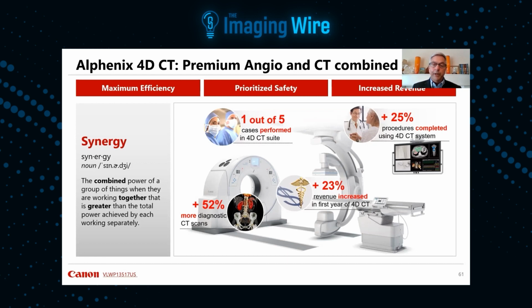And part of the reason was, right now, a lot of departments that do interventional CT use what's called CT fluoro, and they'll have a CT scanner that's dedicated. It might be outside the department or way down at the other end of the department. And they'll have to dedicate that CT scanner to just doing those types of cases. And that means that they have to buy extra CTs to do their diagnostic CT, all those different things come into play. Well, when you put the angio CT in, the 4D CT in the department, because it comes with the ability to do the interventional CT fluoro on the system, plus you have the ability to do needle guidance on the angio system itself, it speeds up the ability to do CT fluoro work, and it puts it all in one room. So you're not transferring the patient from one spot to another.